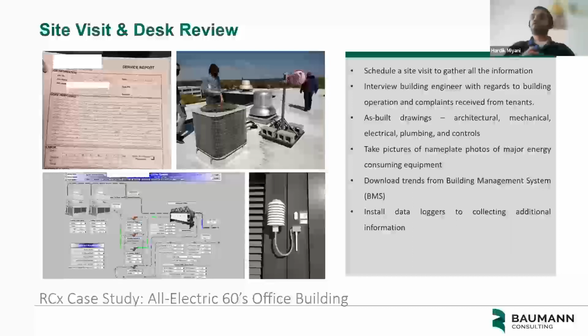And the last thing that we saw for this particular building was, while reviewing the BAS, that the ambient temperature and humidity sensor was providing a faulty reading as compared to the local weather station located very close to this facility. If we look at it, the entire building performance is dependent on the ambient temperature and humidity sensor. If this sensor is not calibrated annually, it can completely impact the overall building performance.